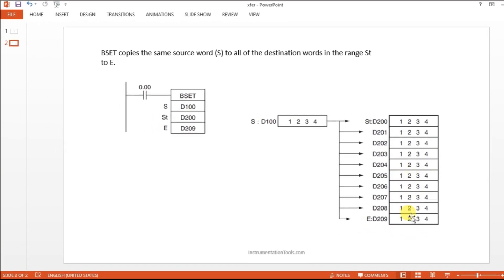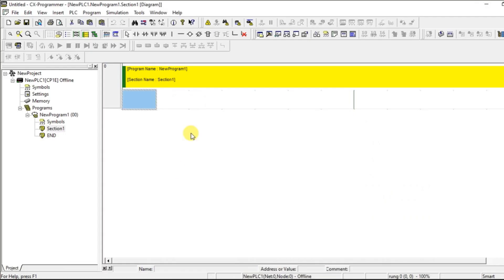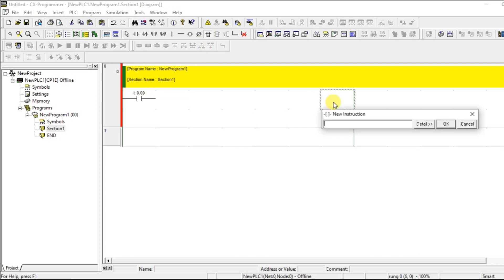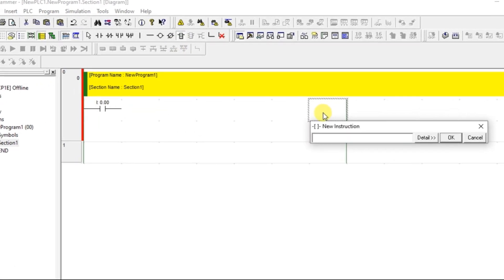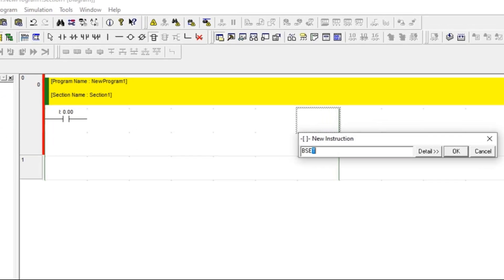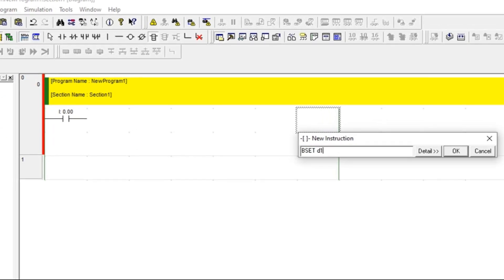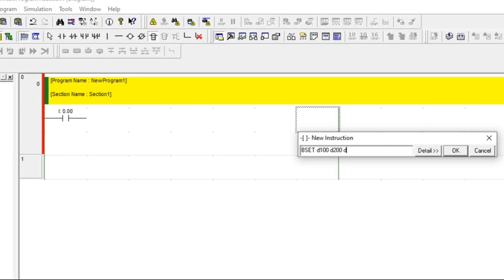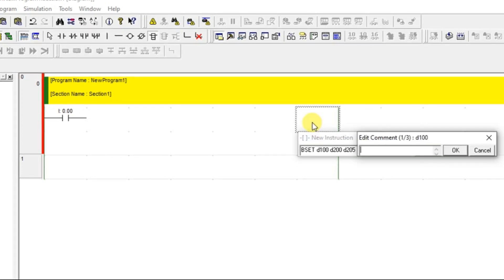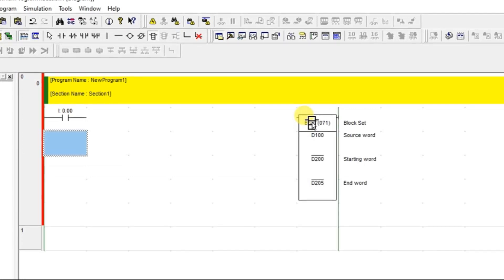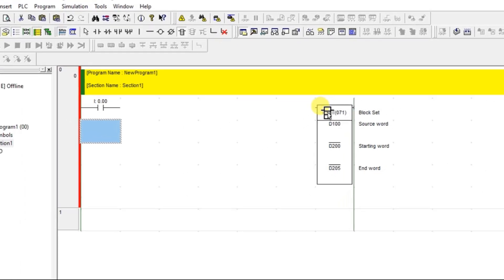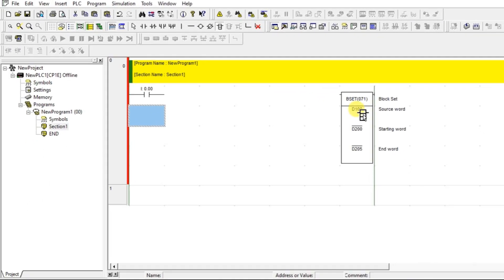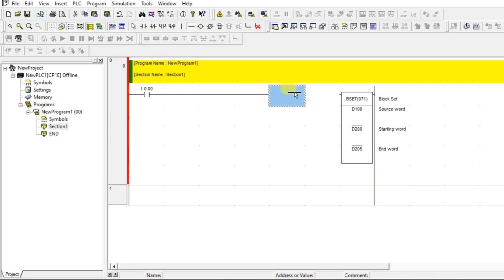Let us see that in the Omron PLC ladder logic. I am going to type BSET and just give one address D100, next is D200, and next I am giving D205. D200 to D205, the data of D100 will be updated. Just connect this.